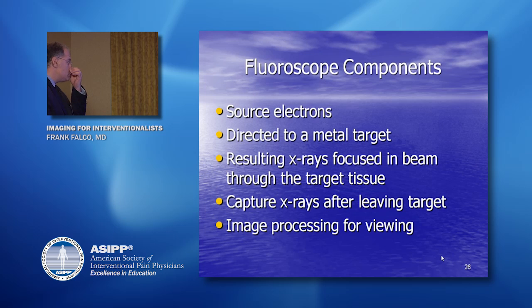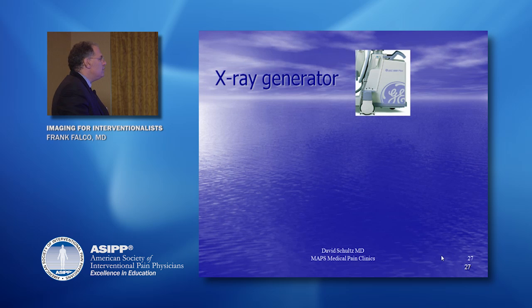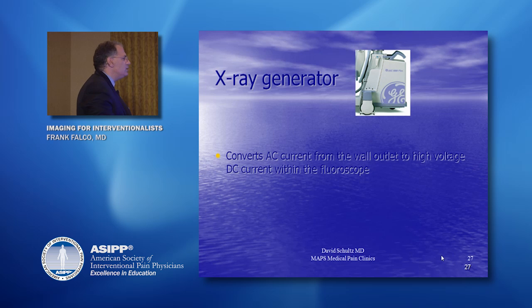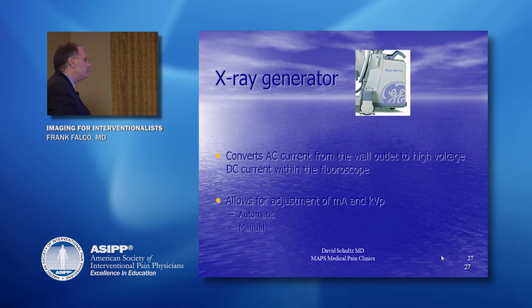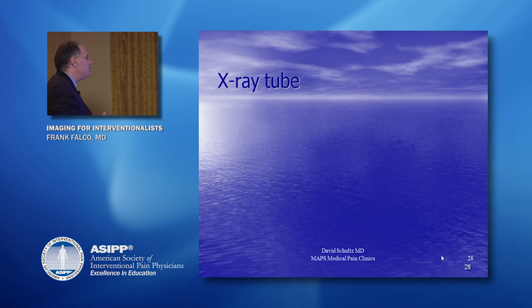So the fluoroscopic components: you have a source for creating electrons and creating irradiation. This results in X-rays. You capture those X-rays after leaving the target on the image intensifier, and then an image is processed and produced on the fluoroscope video screen. This is the generator. This is where you're generating energy that's plugged into an outlet, and this is where you get your direct current. That direct current can be adjusted in terms of current and voltage, either automatically or manually. You can make those changes, which is very helpful, particularly if you have someone who's very thick or very heavy.